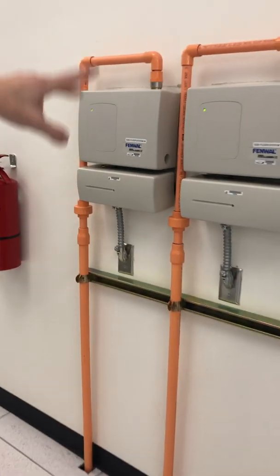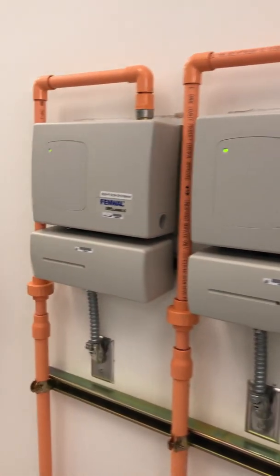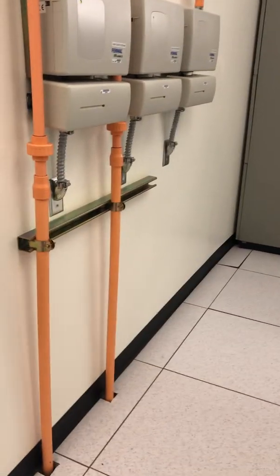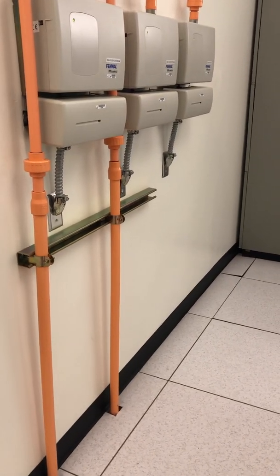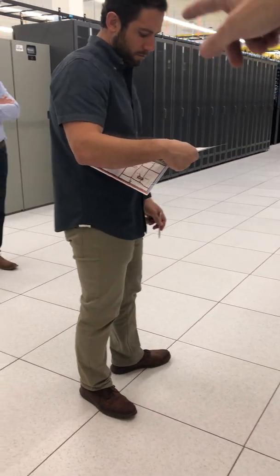Here you can see 3 of the 4 air sampling systems. The other one is down at the end of the room, which we'll go to shortly. It's a preemptive smoke detector. By suction, it draws particles from the orange pipes you see overhead, and the orange pipe I showed you in front of K-row. It draws it in to catch a fire preemptively, before we have to rely solely on the ceiling-mounted conventional smoke detectors. Very cool. In the event of a fire, which should never happen, you want to catch it as soon as possible.